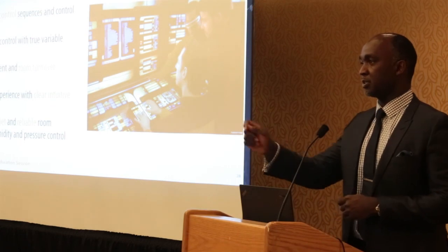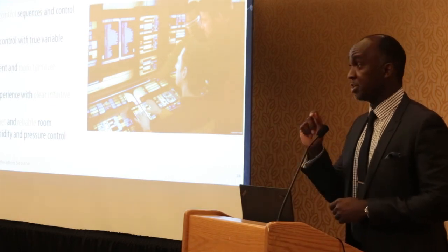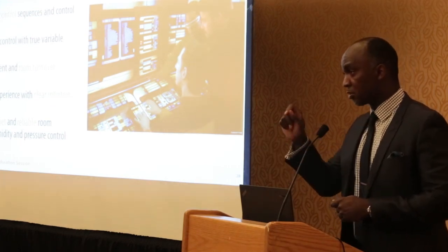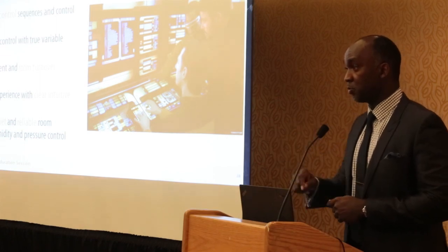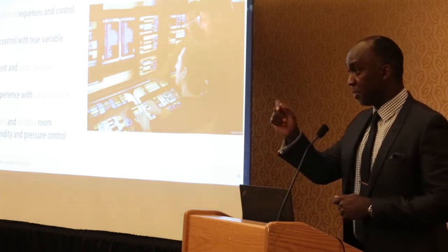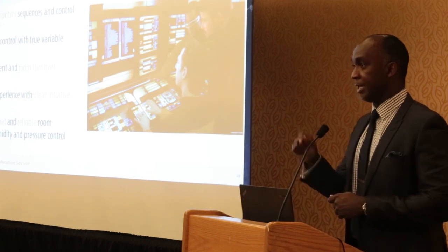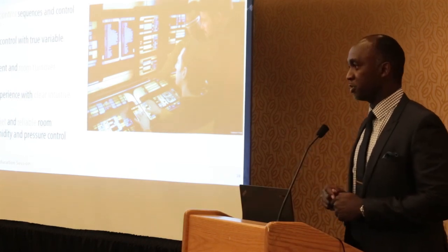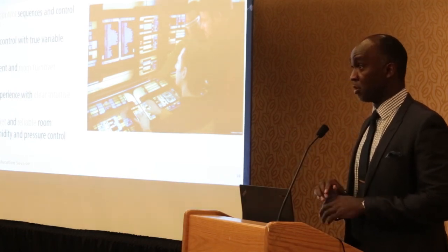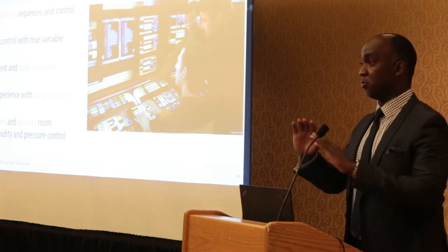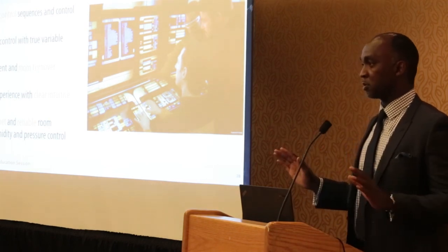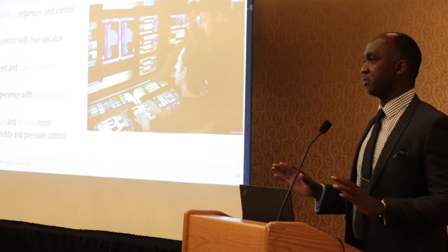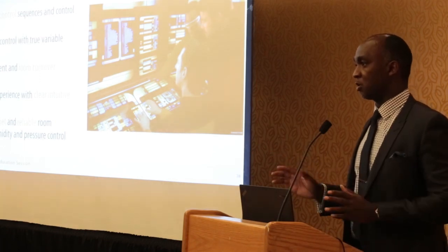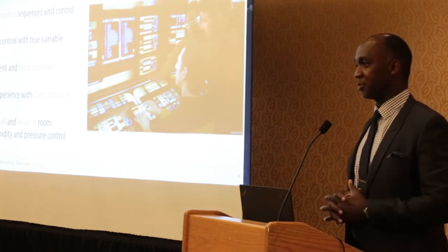Say they don't want the 68 to 75 FGI guideline temperature, they want 62. You can see that the surgeon did his surgery at 8 o'clock, and the temperature he selected was 62 degrees, his humidity was this, his air change was this, and at that time it was a positive pressure of 0.015 inches within the room. So all the FGI conditions were perfect, and the surgery was done under the perfect operational conditions.